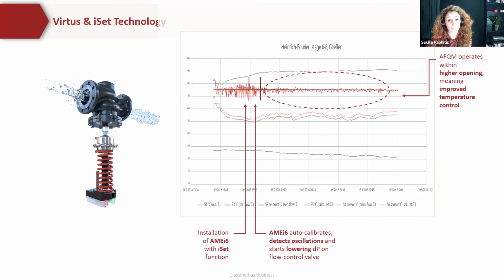As you can see from the graph here, and this is a real life case study that we've been involved in, you can see the benefits of installing this technology. So you can see on the left-hand side that there are big flow and temperature oscillations, and these are measured on the secondary network, especially during the low demand periods. You can see in the middle portion there where iSet has started to kick in, and it's starting to lower the differential pressure control and oscillations. It also shows on this right-hand part of the graph where iSet is fully functioning. It's learned how the demand flows from the heat exchanger and the system itself, and it's starting to provide a much better comfort condition for the end users. So this is the part that's being delivered into your tertiary side of the system.